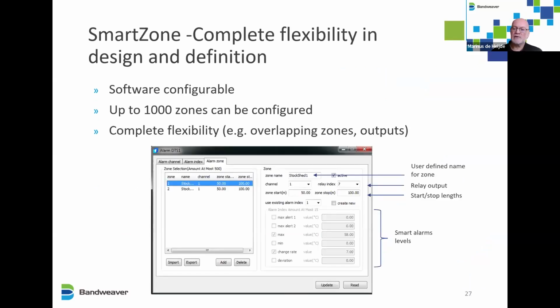This is what it looks like when you need to program the unit. As I said, it's software configurable up to 1,000 zones, which gives you complete flexibility with overlapping zones and different outputs. We can name the zones, so we can have up to 1,000 zones with up to 1,000 different names. We can then have the relay outputs. We can start and stop the lengths. For example, in your control room you've got the unit, and your first conveyor belt is 100 meters away. Your zone will start at 100 meters, and if it's a 20-meter belt, the zone stops at 120 meters.